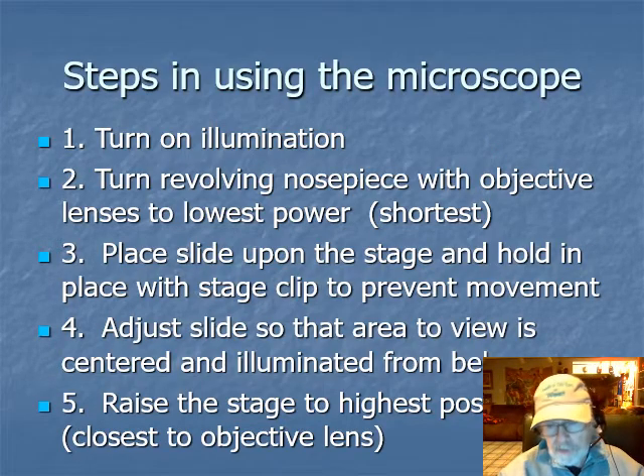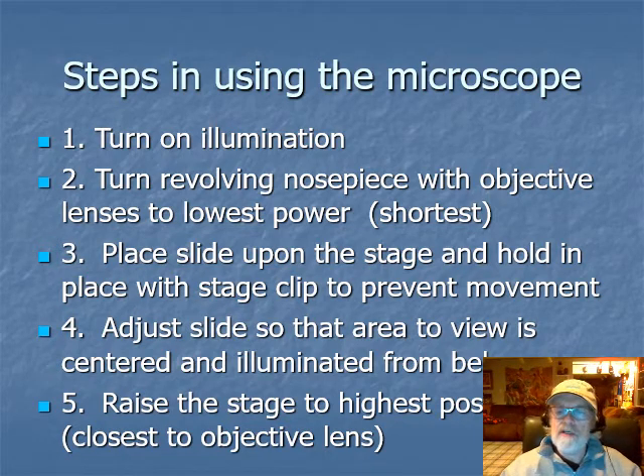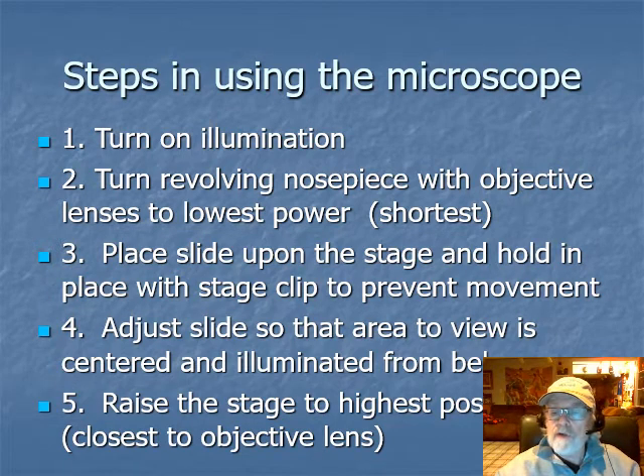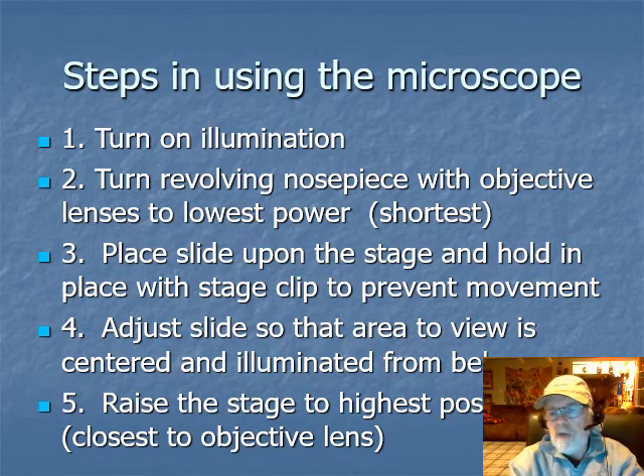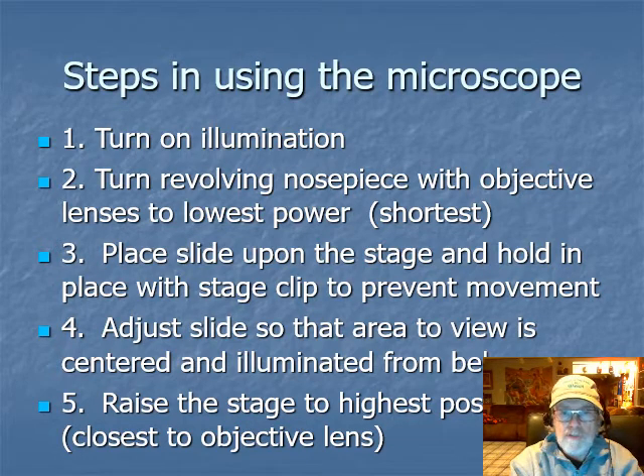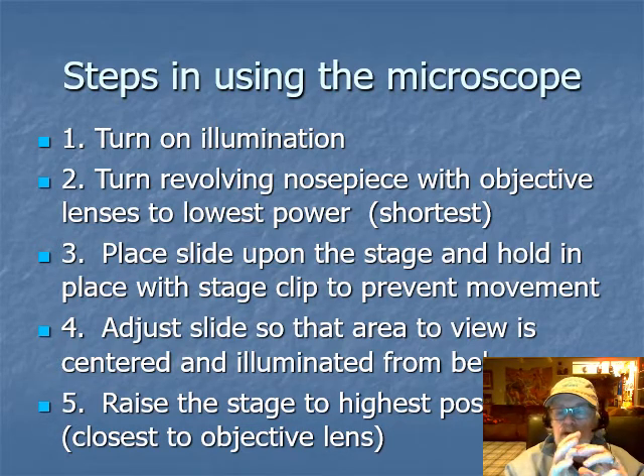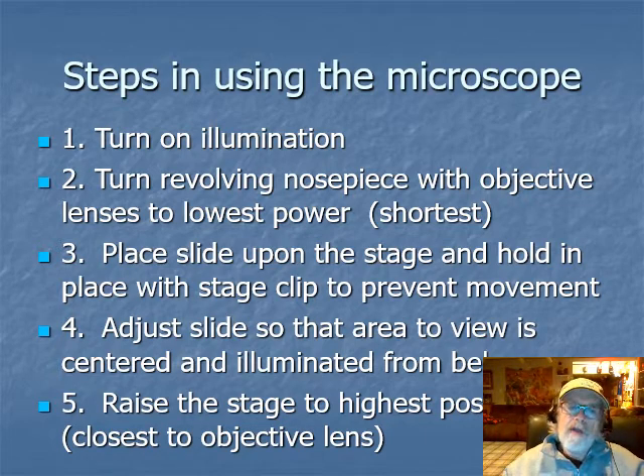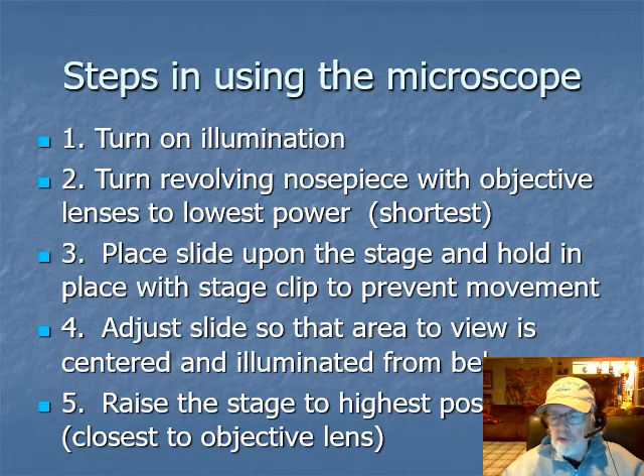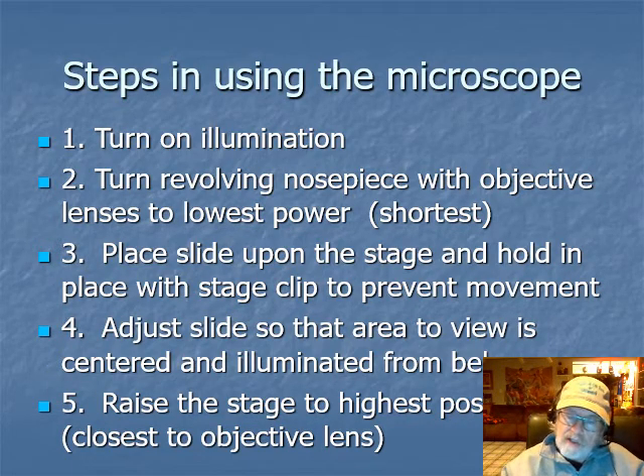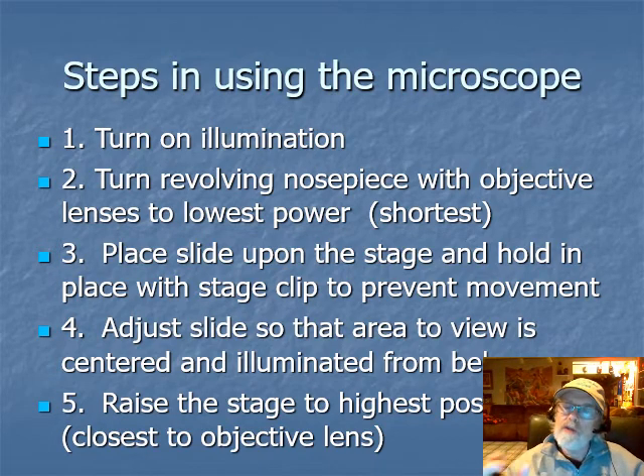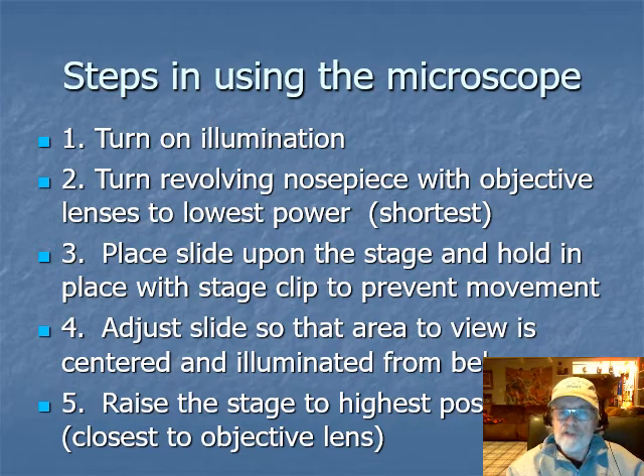Now how do we use the microscope? Again, the more you practice the better your skill. You get the microscope, put it where you need it, plug it in, and turn on the illumination. Then look through the oculars and move them according to your pupillary distance until you have one circular field of vision. Take the revolving nosepiece and put it to the lowest power objective - you should always start looking at the lowest power and then move up from there.